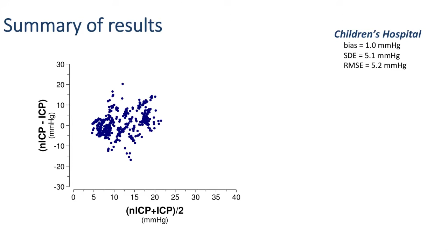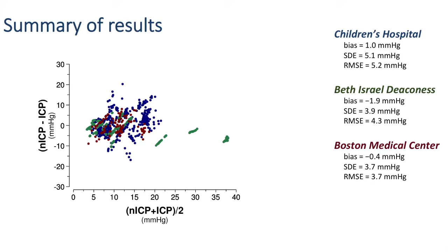At Beth Israel Deaconess Medical Center, we have a magnitude of the bias of about 2 millimeters of mercury with a standard deviation of about 4 and a root mean squared error of 4.3, and at Boston Medical Center, about 0.5 millimeters of mercury of bias, or absolute bias, and a root mean squared error of less than 4 millimeters of mercury. So if we pool all of these results, we get a bias of the method of about 0.7 millimeters of mercury and a standard deviation of the error of 4.9 millimeters, or let's say 5 millimeters of mercury.